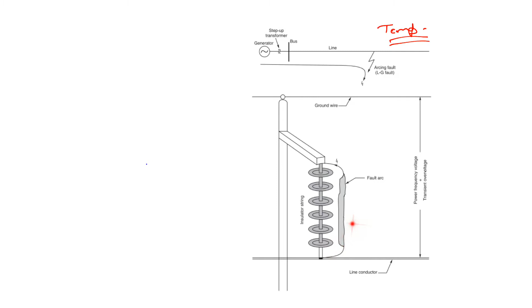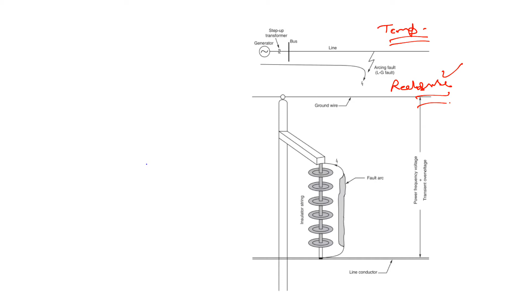This is known as a recloser. We are interrupting the electrical supply for a sufficient period, and the arc does not restrike after the supply is restored. This process of interruption followed by intentional re-energization is known as reclosing. What the recloser is doing is deionizing the path, so that when we again energize the supply, no material is left here through which the current can flow. That is, no conducting path would be there.